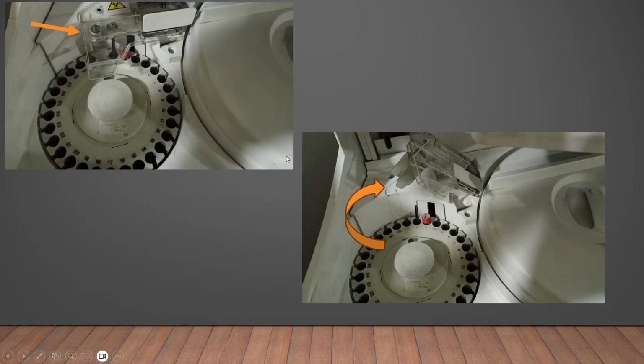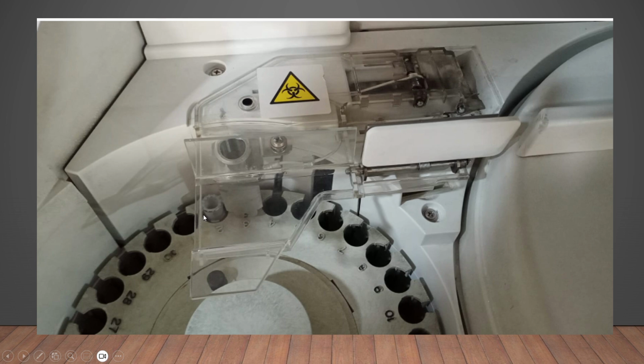As you can see, it can be lifted up and down like this. But the important thing is there is no sensor to tell that this guard is closed or up or anything. So when you start the instrument, there is a very high likelihood that the probe may come and actually hit and break this. Okay, so that's a big problem. So every time you are putting the sample on this disk, you have to ensure that you lift it and then put it back. Lifting and putting it back is also slightly tricky.